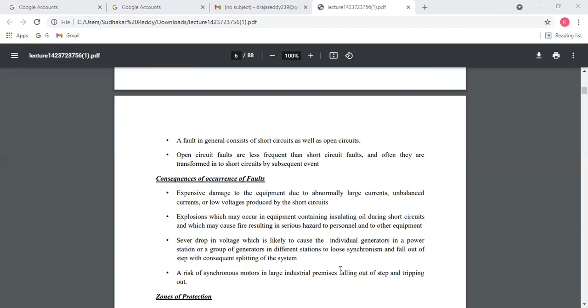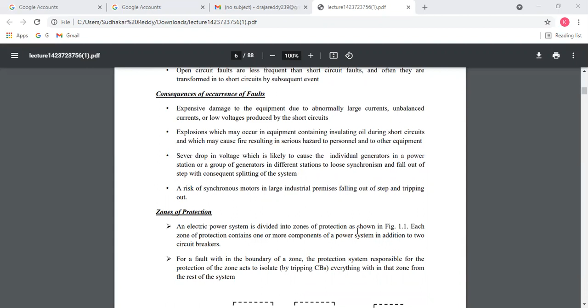Now I will discuss zones of protection. An electrical power system is divided into zones of protection as shown in the diagram. Each zone of protection contains one or more components of the power system, in addition to circuit breakers. For a fault within the boundary of a zone, the protection system responsible for that zone acts to isolate it by tripping the circuit breakers.